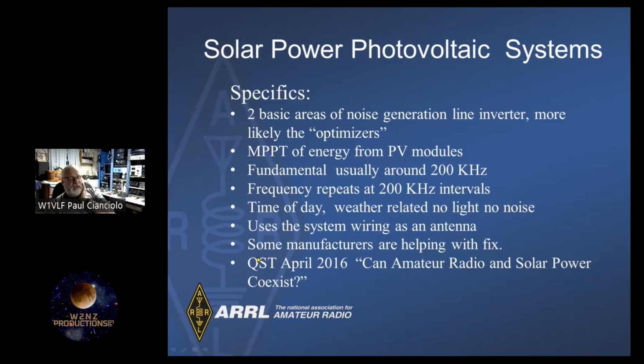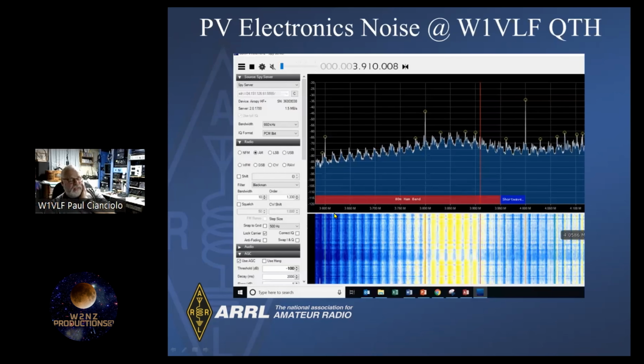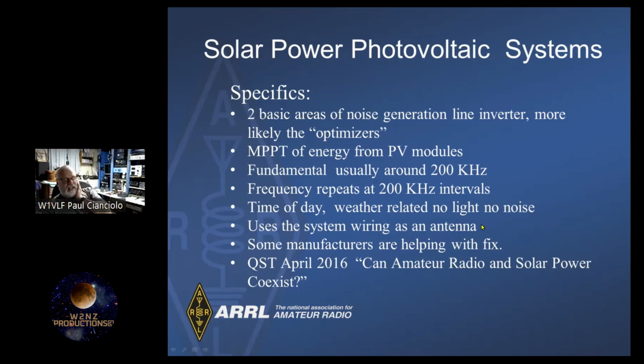So going back here, these optimizers have a fundamental operating frequency around 200 kilohertz. What's this, 3600, 3800, 4000? These are the switching noise from the optimizers, and it goes all the way up to 20 meters, even 10 meters. You're switching 300 to 400 watts per panel, so you get a lot of harmonic energy. The rest of this noise at 18 kilohertz and up is from the inverter, the big wall-mounted line-tie inverter. That's where that other noise is coming from.